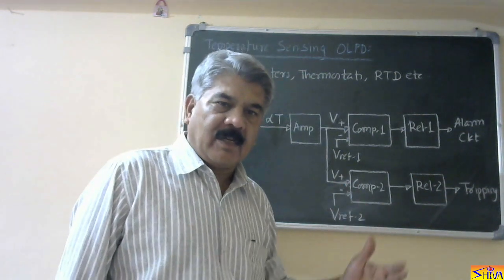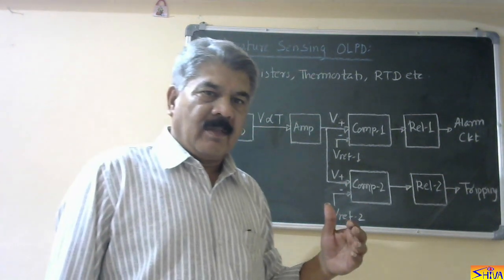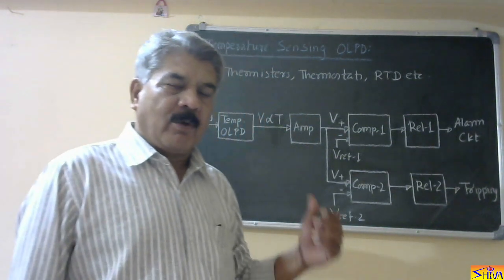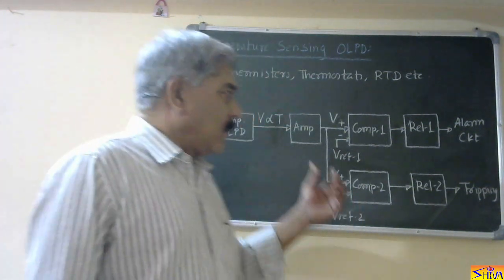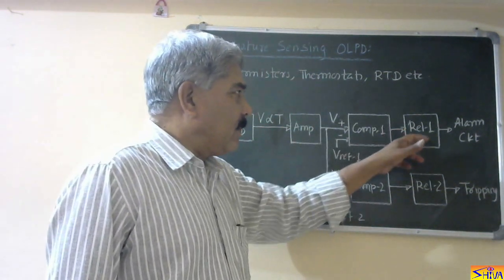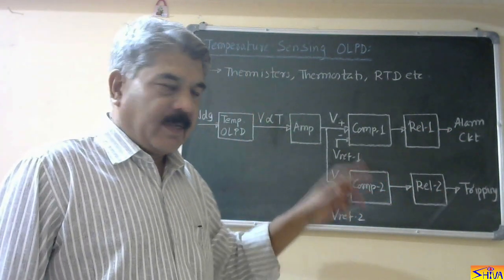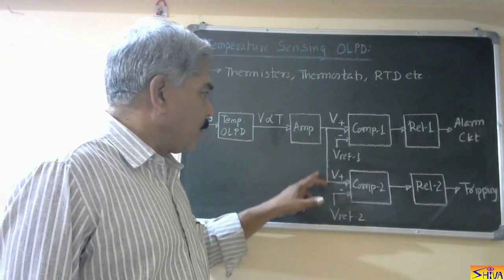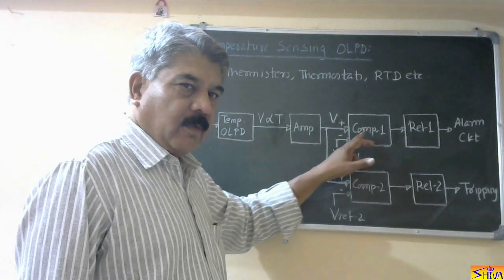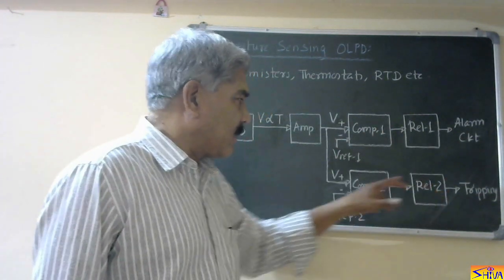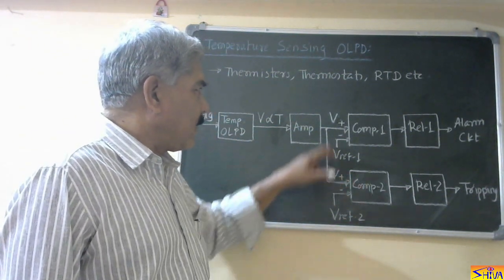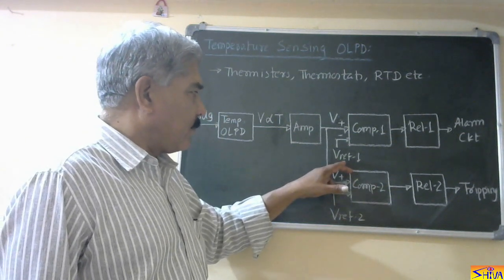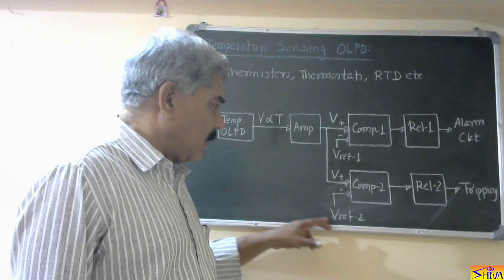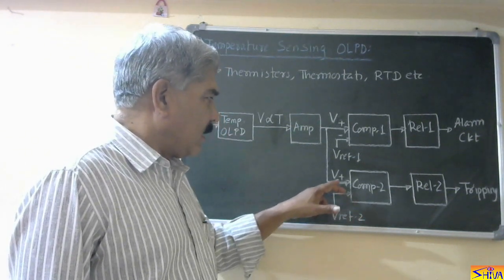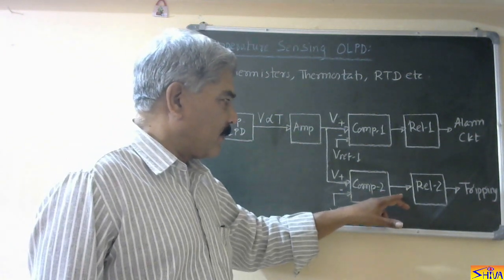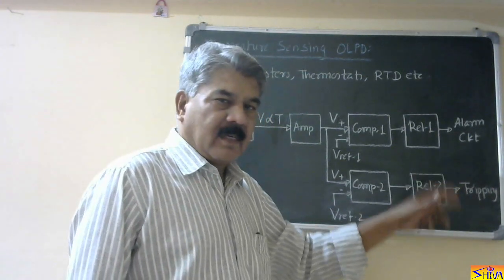Alarm means there is something wrong with the motor, but it does not need disconnection immediately, but it needs attention immediately, because there are some reasons due to which temperature is increasing. This is not mandatory, because this is required when we need alarm as well as tripping. Now when we need only tripping, then this output goes to the comparator. I am showing these two so that you can get the idea about alarm circuit as well as tripping circuit. So it goes to comparator 2. So obviously this reference voltage 2 is higher than reference voltage 1.